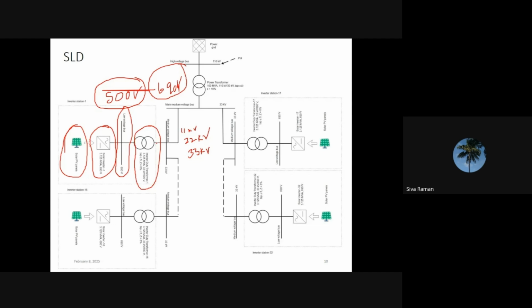Suppose the plant is connected to the medium voltage. The medium voltage value decides the HV side voltage. For most utility scale applications in the megawatt range, for example 50 megawatt and above, it will be connected through the 66 kV voltage level and above. So 66 and above means 110 kV, 132 kV, 200, 220, 230, then 400 kV, for the Indian voltage levels. Most of the time, the plant interconnection bus voltage will be according to the interconnection voltage available at the location. In this example, it is 110 kV. The medium voltage, that is the transformer output high voltage side, is at 33 kV.